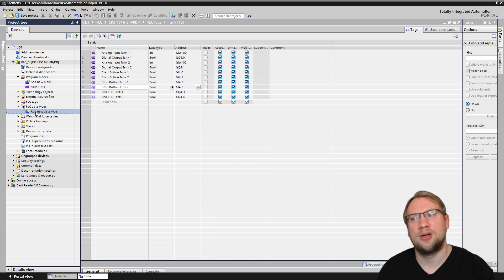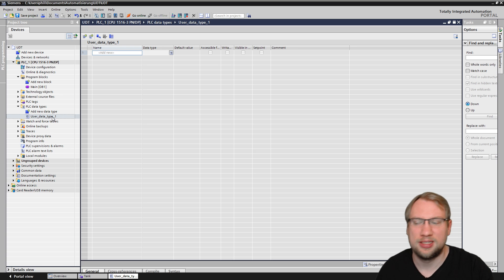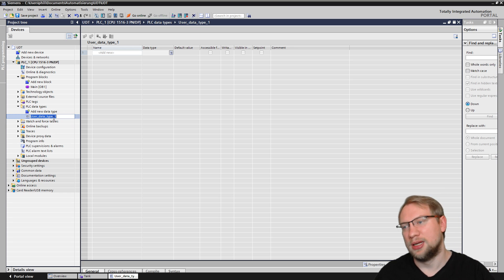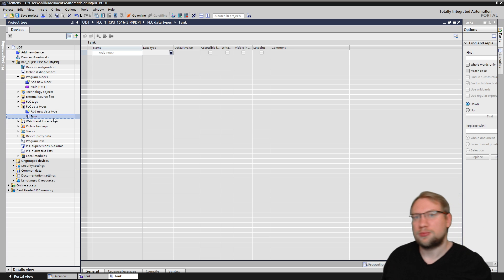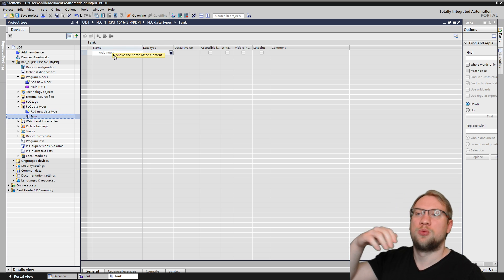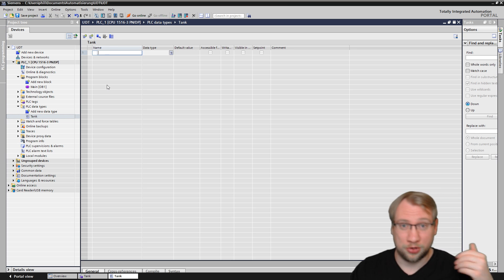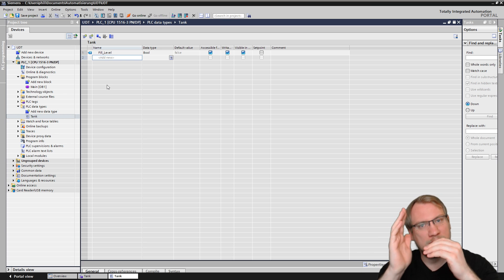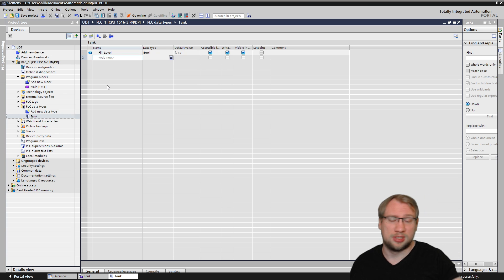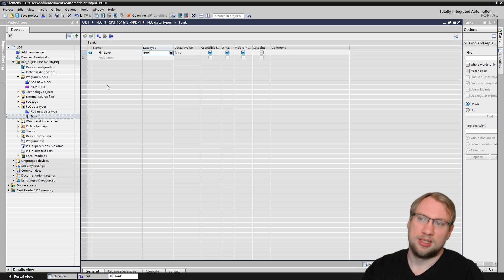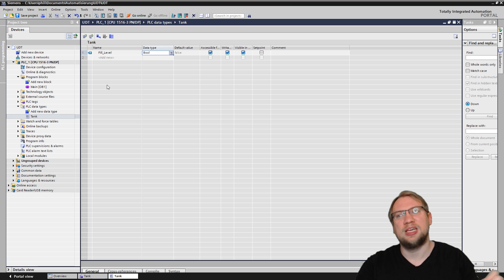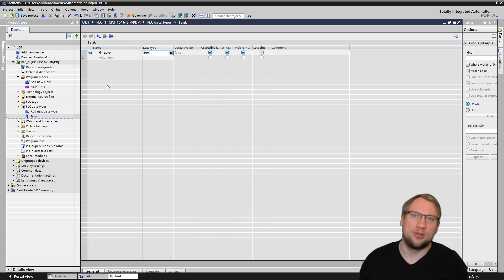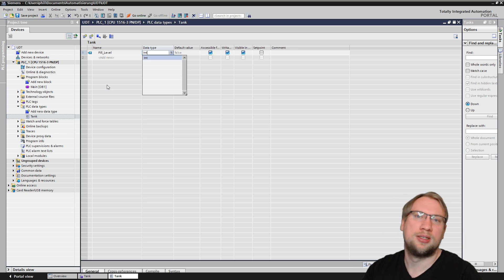It might be that there are already some depending on which functions you use. Some functions, if you implement them in your program, they automatically add specific new data types to your program. But I have not done that here in the program, so this is empty. I can just click here and add new data type. This new data type right now is called user data type. I can just rename it, right-click, rename, or simply hit F2. Or I click in here, wait a second, and click again. And I will say this is a tank. So now I need to define what is a tank? What variables do we need?